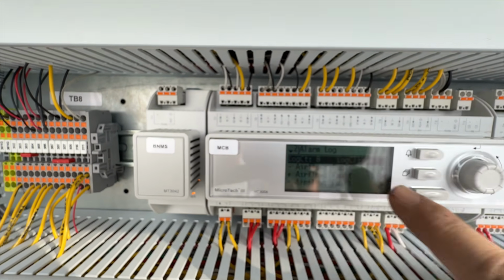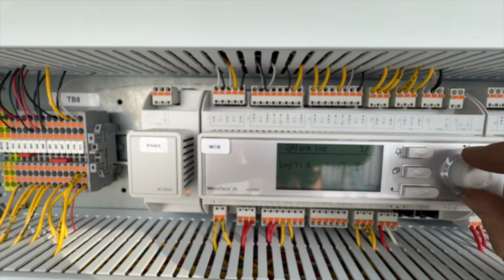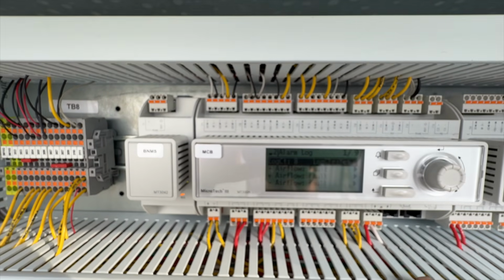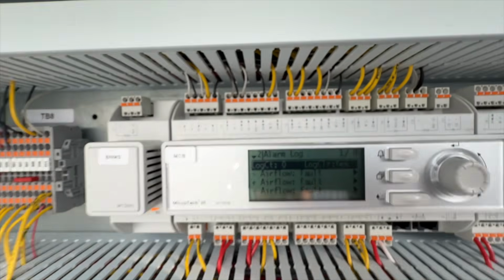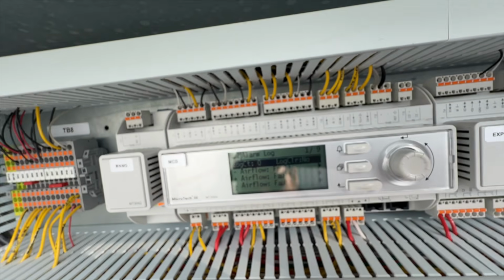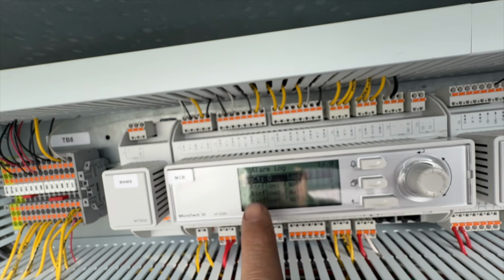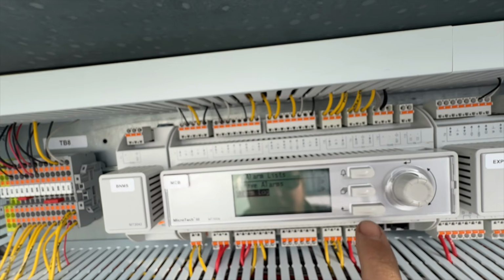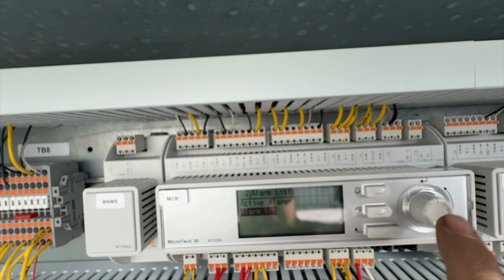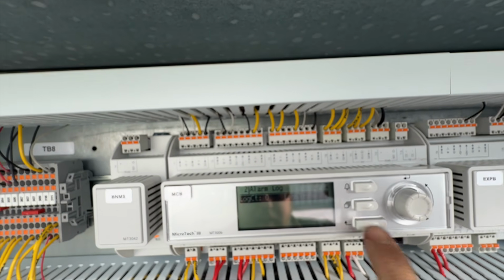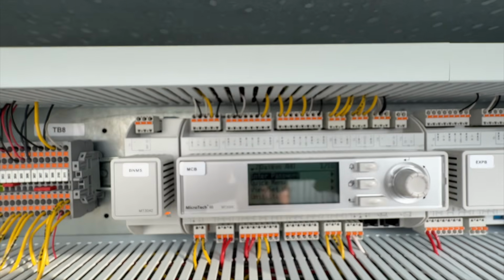So what we're gonna do is clear it. We go to the very top, select that, hit yes, and boom. Every time you do a PM, especially if you fixed a fault, it's a good idea, especially after you kill the power, to clear out your log. Now we can see it's at 0, and if we go back into it, it's all gone. That way we know there's nothing new.